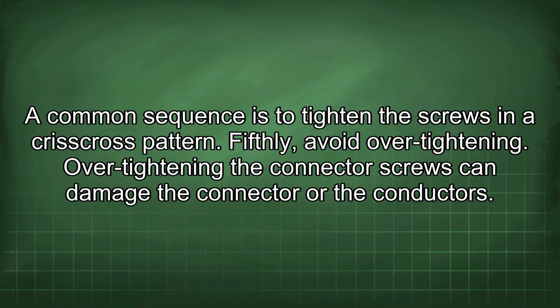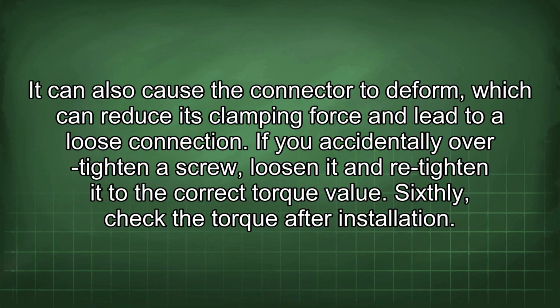A common sequence is to tighten the screws in a crisscross pattern. Fifthly, avoid over-tightening. Over-tightening the connector screws can damage the connector or the conductors. It can also cause the connector to deform, which can reduce its clamping force and lead to a loose connection. If you accidentally over-tighten a screw, loosen it and retighten it to the correct torque value.